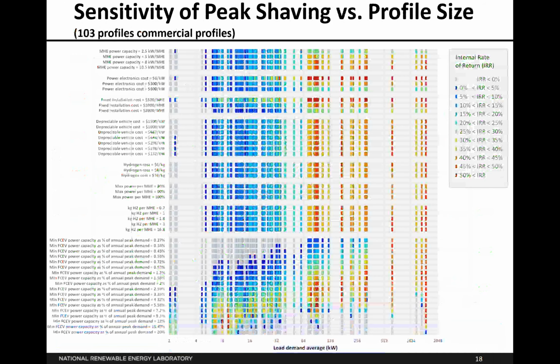This analysis shows in color a sensitivity for all the profiles and parameters, with blue indicating less favorable IRR and red indicating more favorable IRR. Throughout all the profiles, cheaper power electronics tend to push us into the red, which is higher internal rate of return. A more favorable installation cost also gives a better return on investment. Again, we see that the larger the profile, the less we want to peak shave, with the red occurring at a shallower depth.